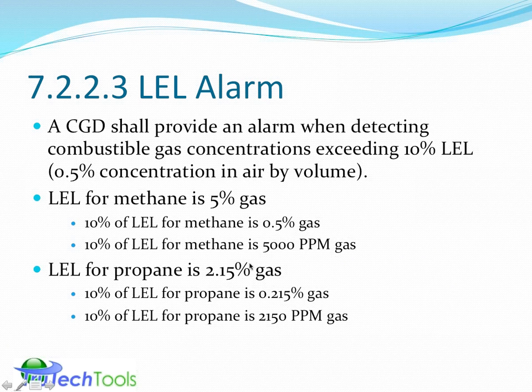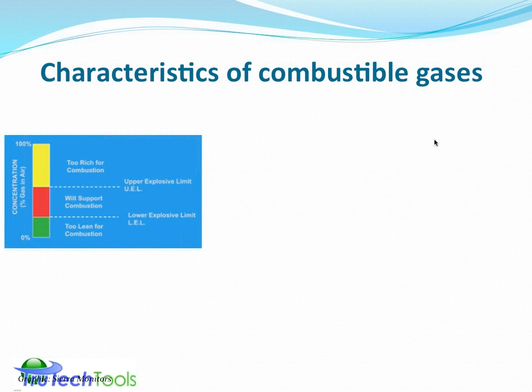So that's one of the feedbacks that I've given and other people have given to the standard. So we want to make sure that it's correct across all types of fuel gases, and the two most common in use are methane and propane. So really what they're looking for is 10% of the lower explosive limit. There should be an alarm that goes off to tell you that there's that concentration of gas in the area, in the vicinity. Now let's take a look and understand what this lower explosive limit means kind of in the real world. What is the science of it?